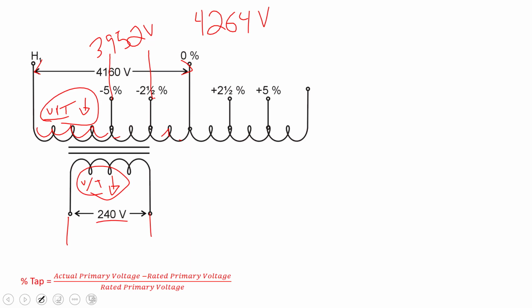It's on, I believe, page 34, but if it's consistently higher, well, if I left it on the 0% tap, my volts per turn would be too much. So I need to add more turns to get that ratio where it should be. So I have to add turns if my primary voltage is too high. If I don't add those turns, I will go higher than 240. So it'll be out of range, right? So it'll be too high, which isn't good for your equipment either.